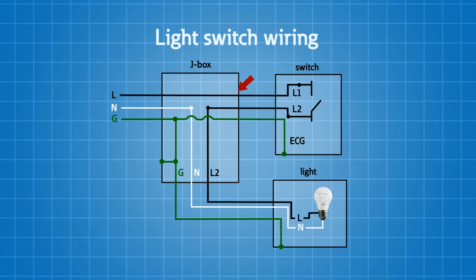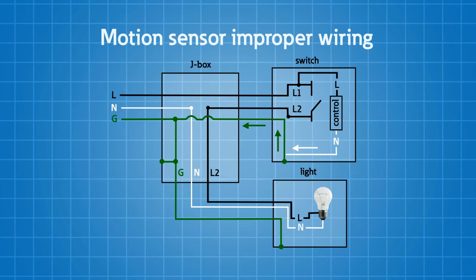If you think about how we wired residential homes or any types of structures when we came down to a light switch, what did we do? We brought one set of conductors, and that was our hot conductor. And we brought an equipment grounding conductor as well. And we did not bring a neutral. When we had a standard light switch, that was perfectly fine because we're just breaking one conductor. But when you install a product like a motion sensor switch, which needs to have power, you need a neutral conductor to provide the potential voltage to power up electronics. If I opened up a light switch and I don't have that neutral conductor there, I could get that power by taking hot to ground, the equipment grounding conductor, to power up that unit, and it will work. But it would put current over the equipment grounding conductor.